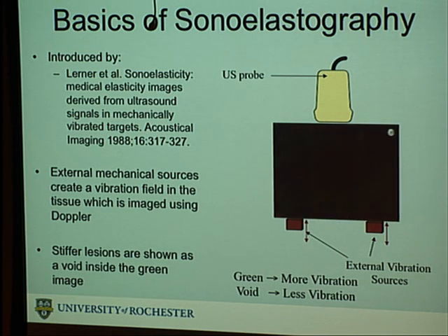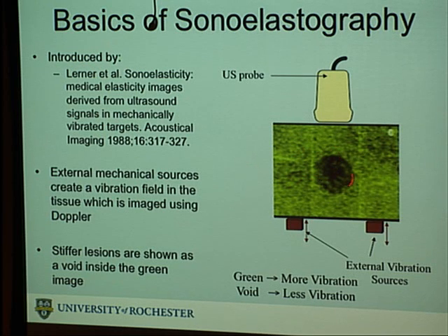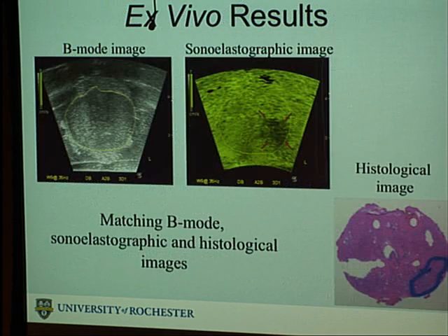And then when we turn on the Doppler imaging and turn on the vibrations, we get images that look like this, especially in phantoms, because we made this thing like 5 times more stiff than the surrounding tissue, so we get these really great images. Anyhow, over time we demonstrated that a dark lesion is a sign of a hard region in an otherwise soft tissue.